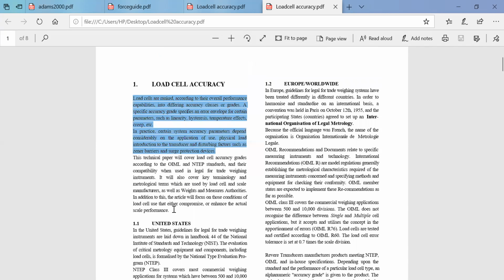But the next paragraph tells you what factor the paper is focusing on exactly. So this technical paper will cover the load cell accuracy grades as per OIML and NTEP standards. You will come to know what these standards are. So they are deriving the grades for load cells based on some standards and also on their compatibility when used in legal for trade weighing instruments. So you will be using these load cells for high weight, low, medium also. Depending upon the grade of weighing instruments you are using, that also could be classified.